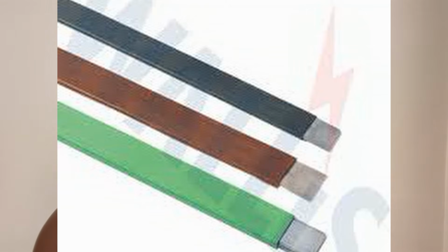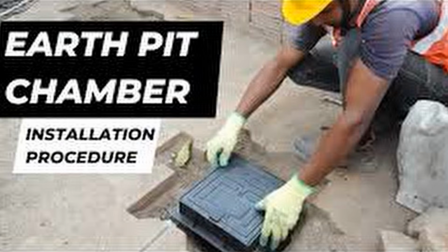But it is harder to install. The metal is physically harder than the copper. So your electrician may charge you a bit more labor, because it's going to be more frustrating and need more muscle power for him to install that aluminium down conductor, but it is cheaper, okay? Then you have the direct connection to the foundation earth. That is your lightning protection system. Air termination rod, some people call arrestor, down conductor, copper or aluminium with insulation around it, on the surface of the building or inside the plaster, as long as there's insulation around it, yeah? And then the direct connection to the foundational earth. The goal is to control the discharge, okay? That is your lightning protection system.